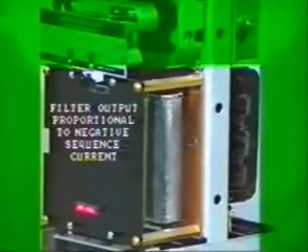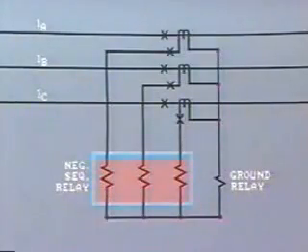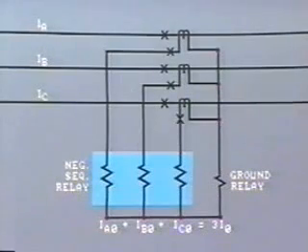The presence of these components provides a useful tool for detecting unbalanced conditions and ground faults. For protection, both zero sequence and negative sequence relays are installed. Typically, the negative sequence relay works by comparing voltage or current in all three phases and filtering out negative sequence components. The current coils are connected to CTs like this. The current flowing through each coil will be the sum of positive, negative, and zero sequence currents in that particular phase.